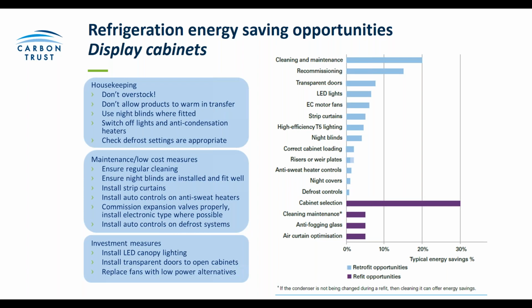And do check the defrost settings of your cabinets and make sure that these are set appropriately to match the conditions of the environment and to avoid any unnecessary heating where possible. In terms of maintaining your display cabinets and some good low-cost measures of energy saving, it's good to have a frequent and useful cleaning schedule. So this will maintain the top efficiency of the product and a good overall temperature control.